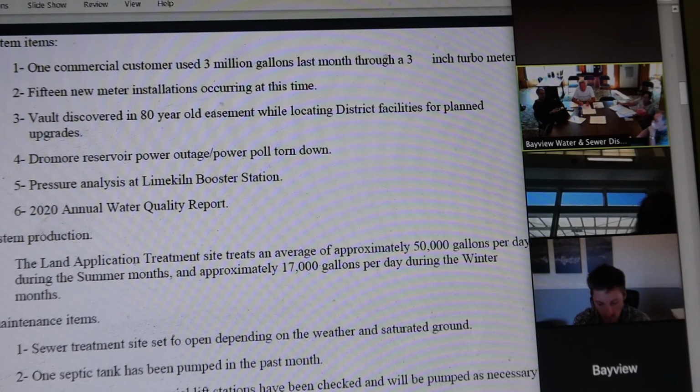That's good. I wanted to bring it up because we're always thinking of one pressure, the static pressure. We need to consider that the pumps are putting out 340 gallons a minute and what that does to pressurize the lines. The point is we go with our eyes wide open. Yeah. When we were considering that before, we thought the pressure coming out of the Cape Horn was 125, or 105 or something. It varies, depending on the tank levels and the usage that's going on in the summer too.